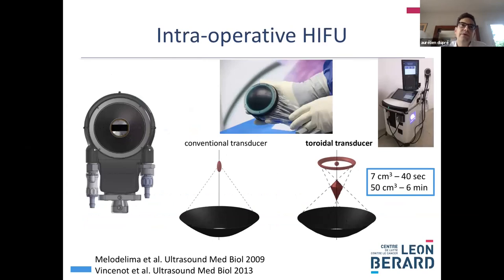So the strategy of our lab's research was to develop an intraoperative HIFU device which would be able to perform large ablations. So in the center here you have the HIFU probe that can be held in your hand. In the center of the probe you have an ultrasound probe for targeting and ultrasound imaging, and all around the ultrasound probe you have the HIFU emitters. With extracorporeal devices, the conventional transducers are spherical, and you obtain ablation of only rice grain size.